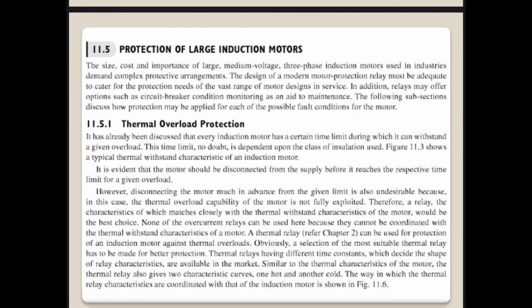None of the overcurrent relays can match or coordinate with the thermal withstanding characteristics of a motor, and disconnecting the motor much in advance of the time limit is undesirable. Your motor still has some capability to withstand the temperature, and as I said, no overcurrent relay coordinates with the thermal characteristics of the motor. So we use a thermal relay which has similar characteristics to the induction motor for temperature versus current. Thermal relays having different time constants are available in the market.